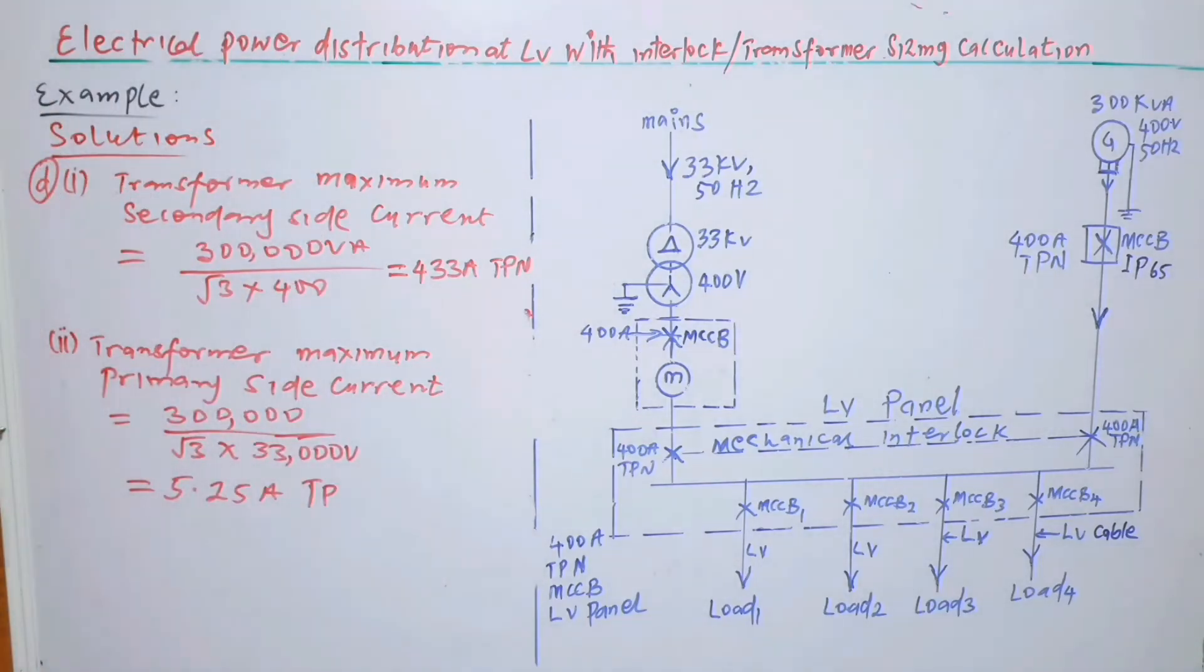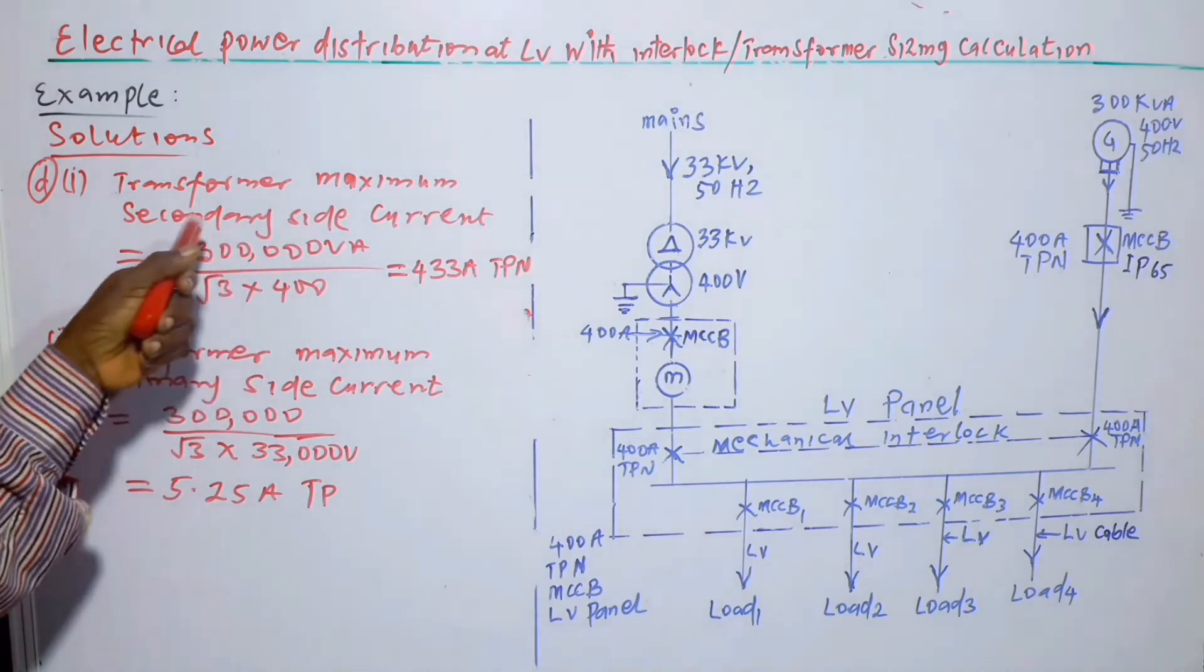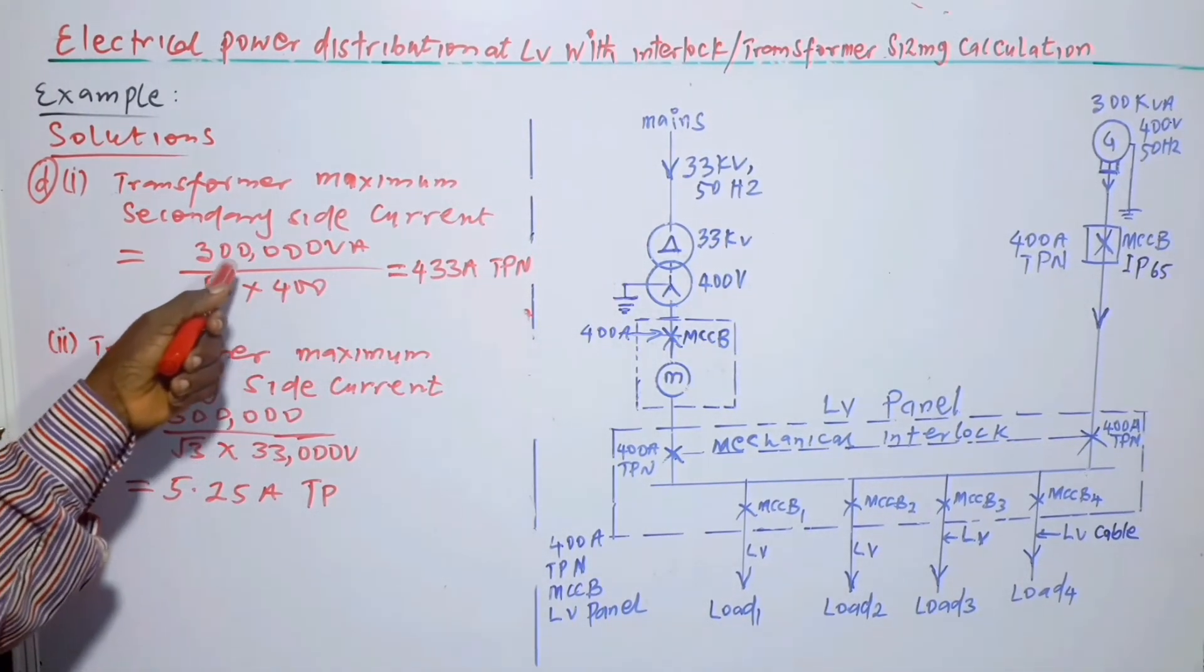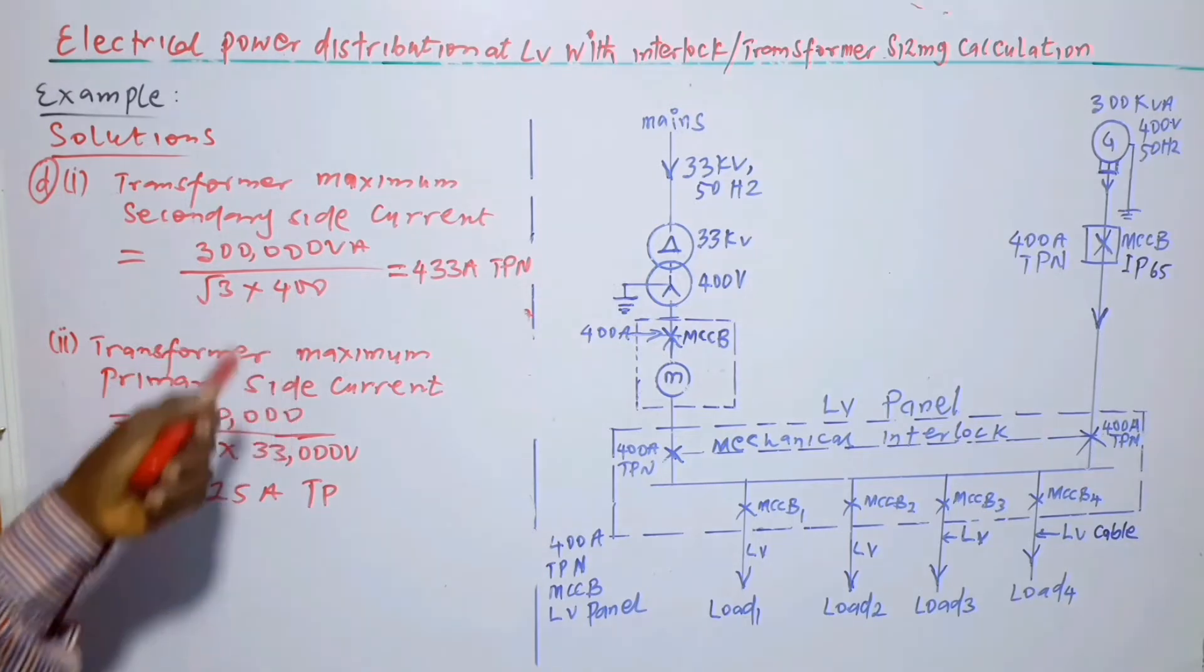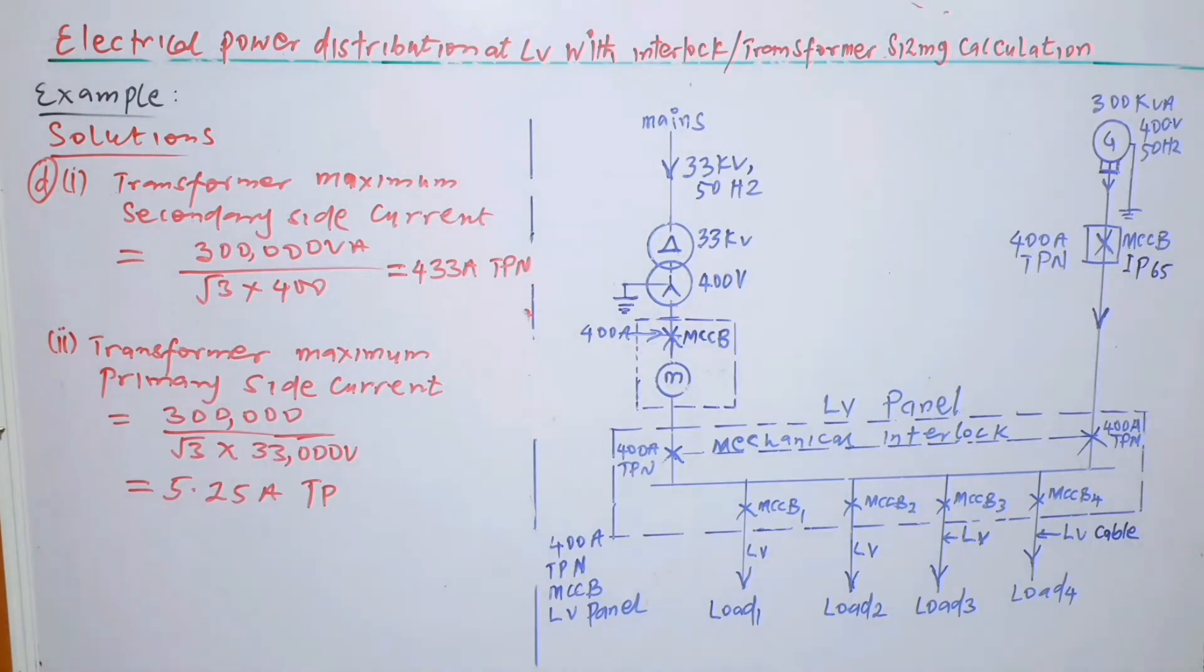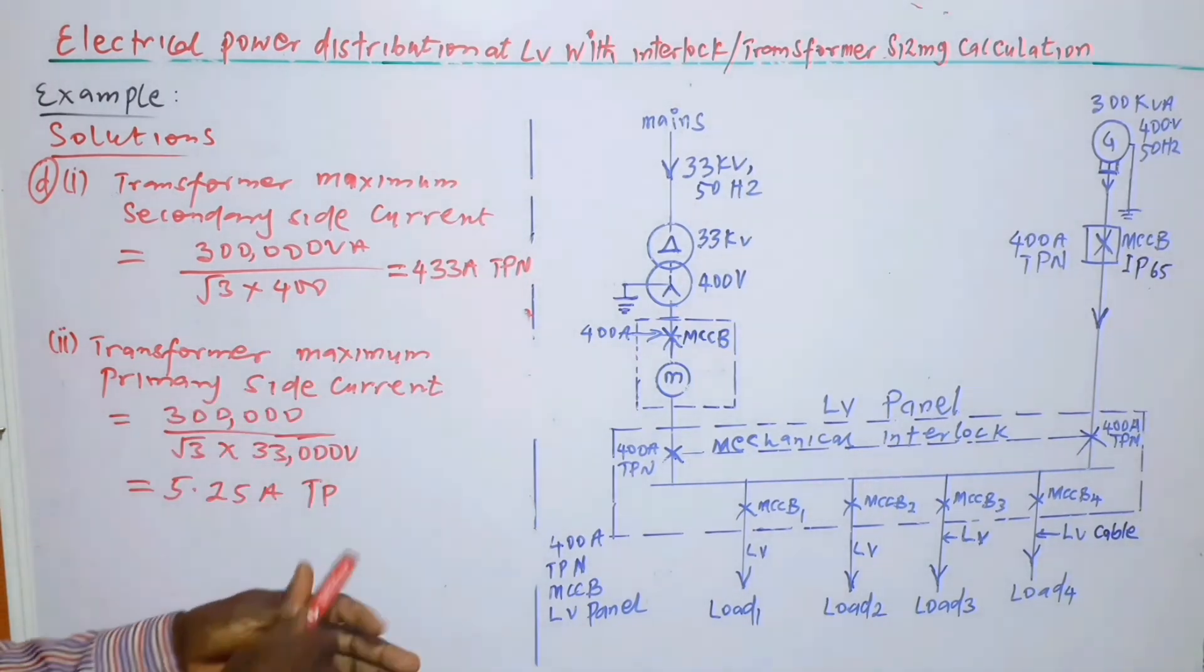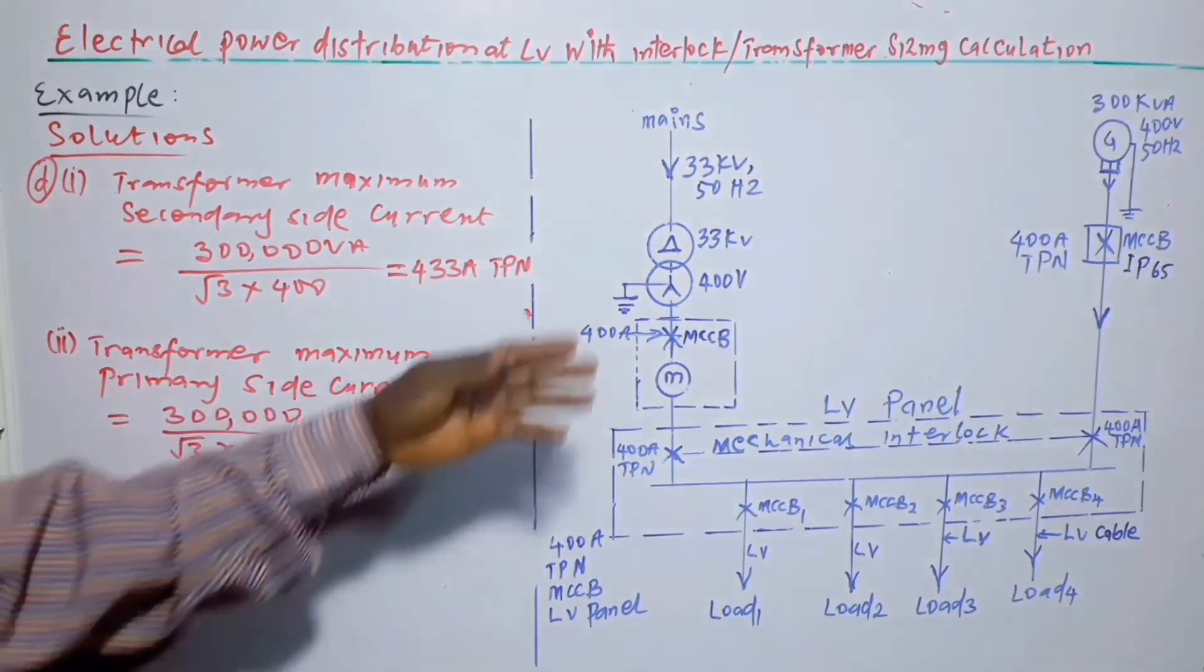One can move a step further by having part D. So part D1: transformer maximum secondary side current is equal to 300,000 VA divided by root 3 times 400, and the answer is 433 ampere. So we are talking of this star side, the secondary side.